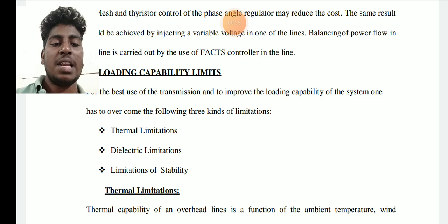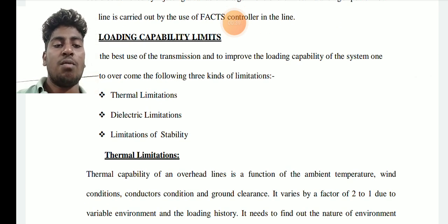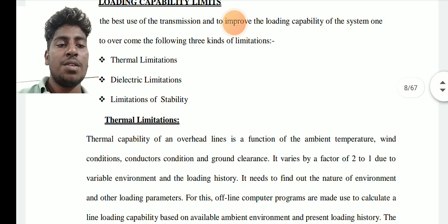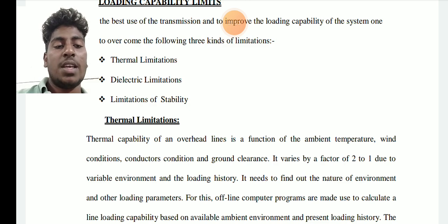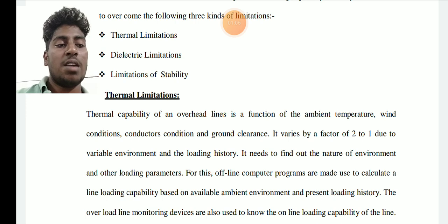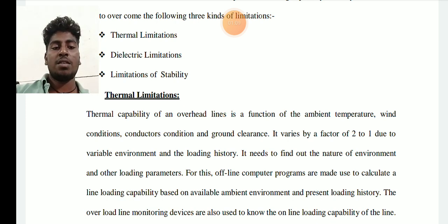First one, thermal limitations. Thermal capability of an overhead line is a function of the ambient temperature, wind conditions, conductor conditions and ground clearance. It varies by a factor of 2 to 1 due to variable environment and the loading history. It is necessary to find out the nature of the environment and other loading parameters, using offline programs or online mode, to calculate a line loading capability based on the available ambient environment and present loading history.